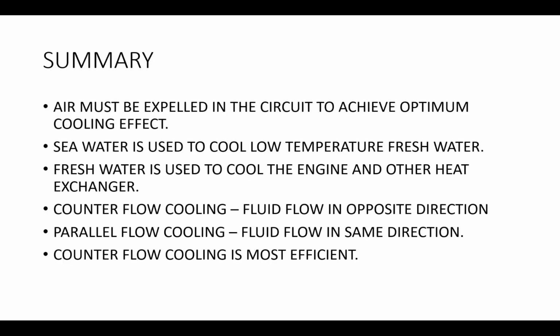To summarize, air must be expelled from the circuit to achieve optimum cooling effect. Seawater is used to cool low-temperature fresh water. Fresh water is used to cool the engine and other heat exchangers. In counterflow cooling, fluids flow in opposite directions, while in parallel flow cooling, fluids flow in the same direction. Counterflow cooling is the most efficient cooling flow.